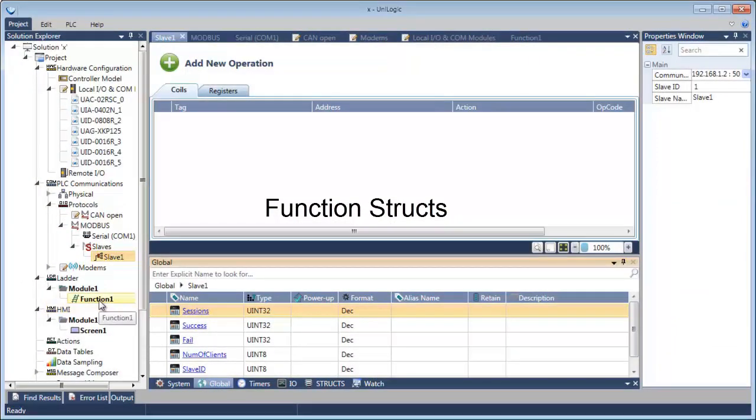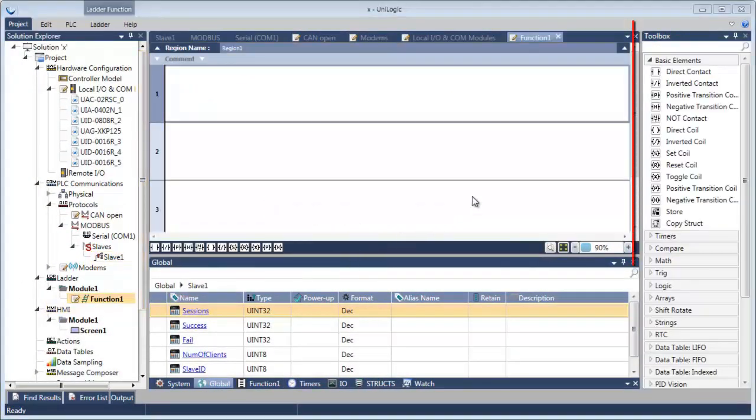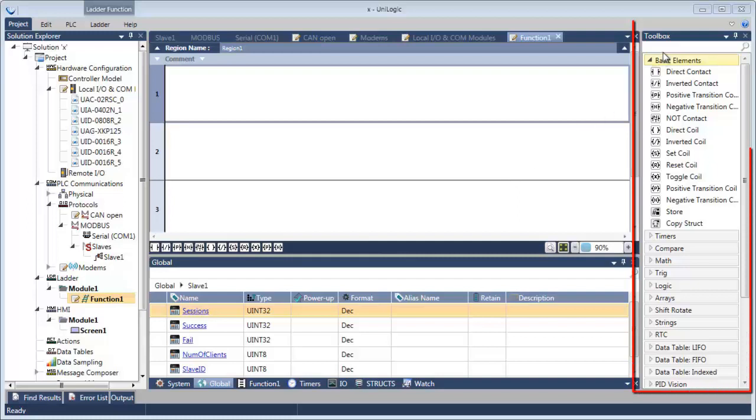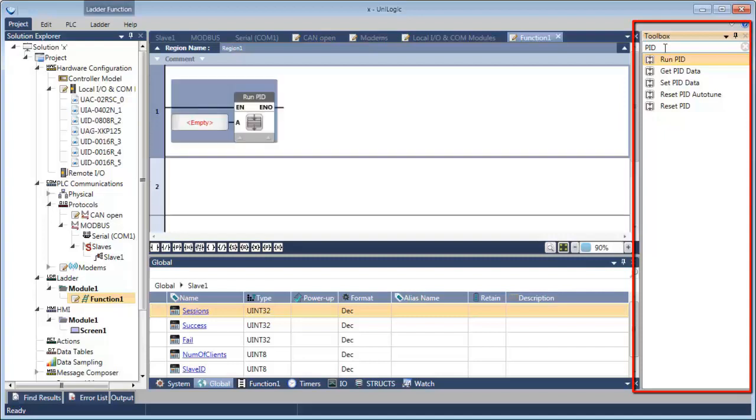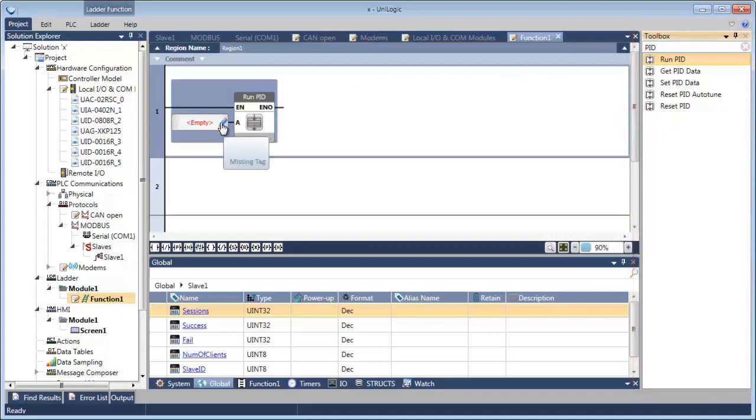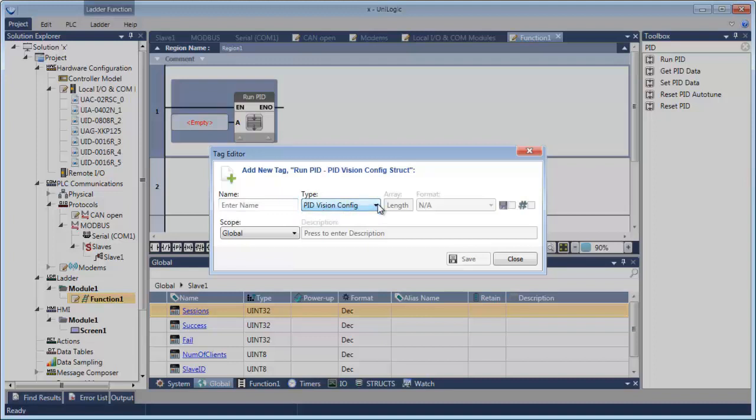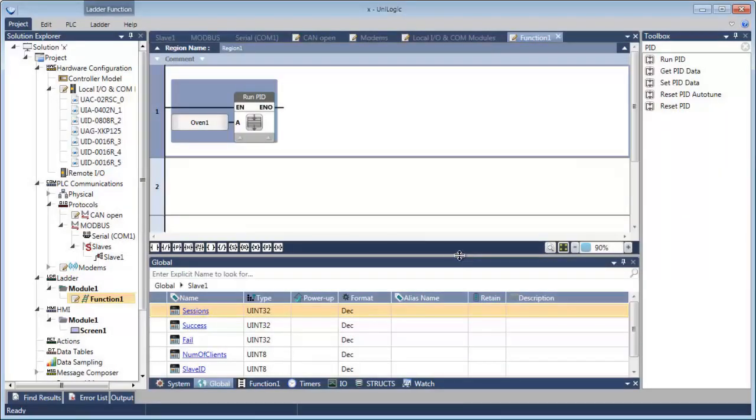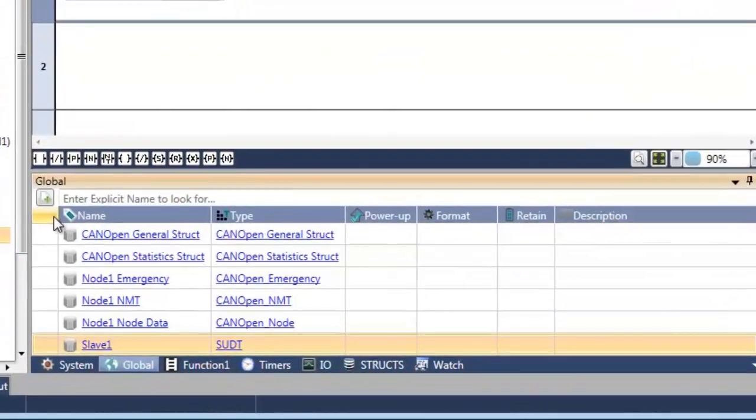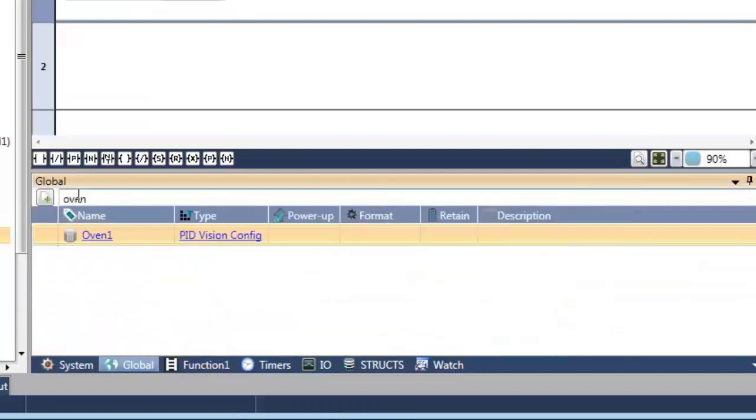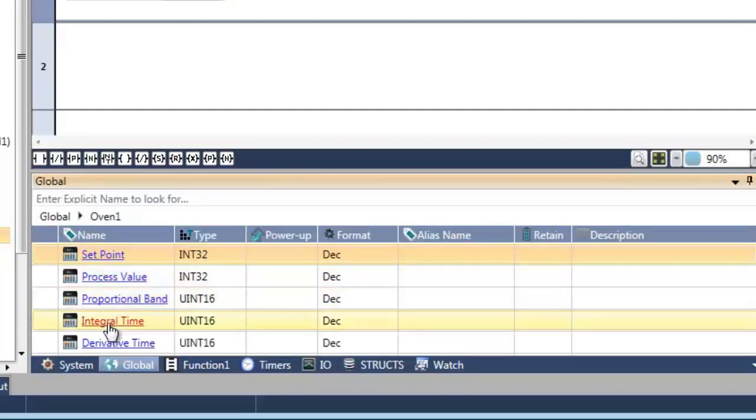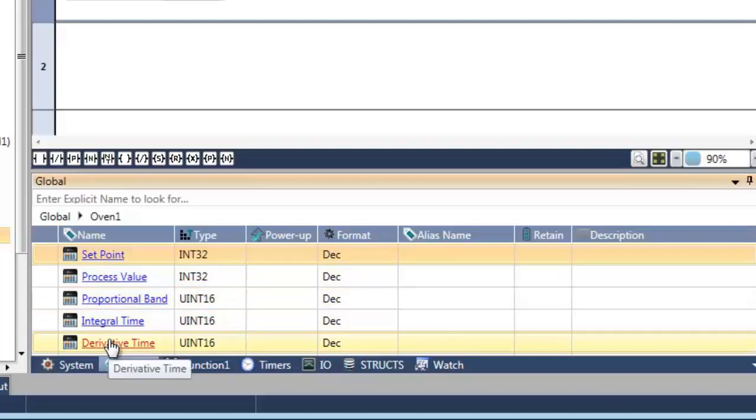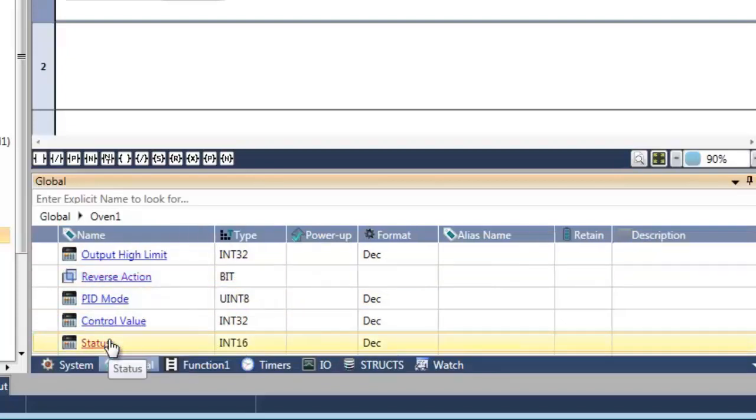Function structs are particularly useful. I'd like to show you what happens when we add a PID function to the application. I'm going to type PID into the toolbox, add a function, and click on the little pencil over there. Now look, the only type that's available is the PID vision configuration. Now we're going to name that tag Oven1 and save it. Now look at this struct. Let's take a look at that oven. You've got your set point, your process value, proportional band, integral, derivative. Scroll down. Reverse action bit. All you need.